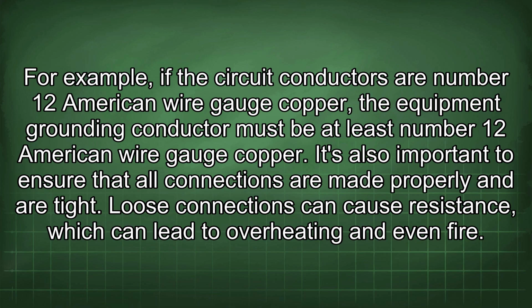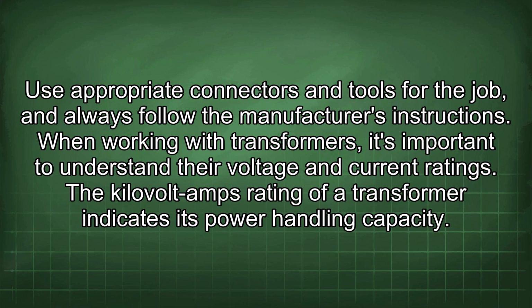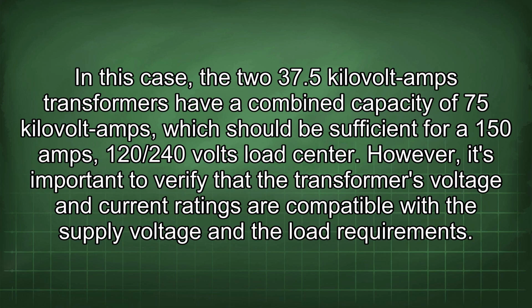It's also important to ensure that all connections are made properly and are tight. Loose connections can cause resistance, which can lead to overheating and even fire. Use appropriate connectors and tools for the job, and always follow the manufacturer's instructions. When working with transformers, it's important to understand their voltage and current ratings. The kilovolt amps rating of a transformer indicates its power handling capacity. In this case, the 2 37.5 kV amps transformers have a combined capacity of 75 kV amps, which should be sufficient for a 150 amps, 120/240 volts load center.